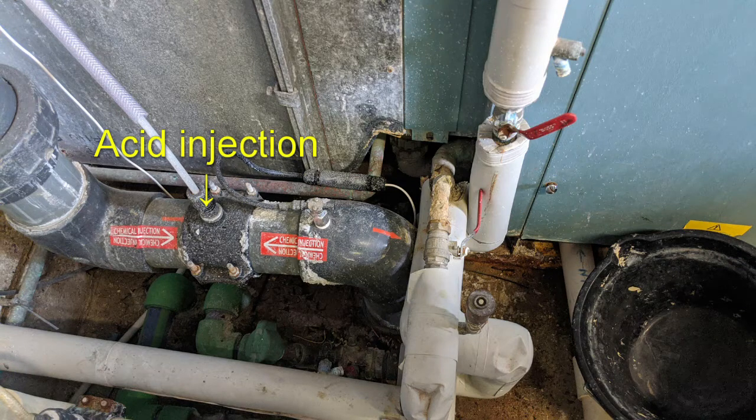You wouldn't want to ideally inject it prior to the heat exchanger, etc., because that would do a fair bit of damage. Sometimes you can have acid being dosed in pre-filter, not often, but again, the only way to know for sure in your plant room is to trace that chemical feed line and see where it comes from. If you've got a UV system, your chlorine or whatever you're using as a disinfectant should be dosed downstream of the UV system as well. So find out what the case is with your pool. It's important to know where your chemicals are injected.